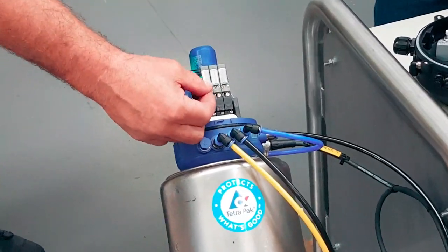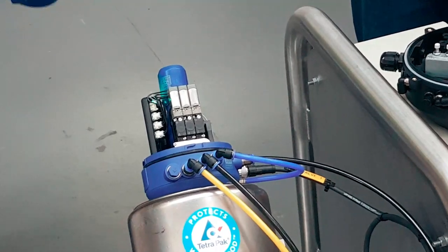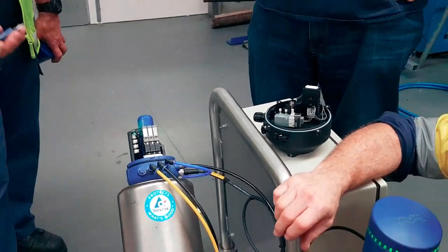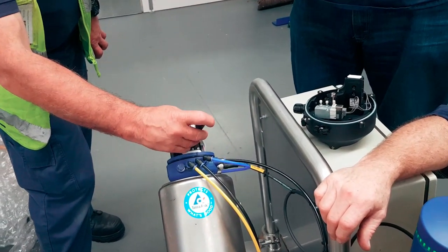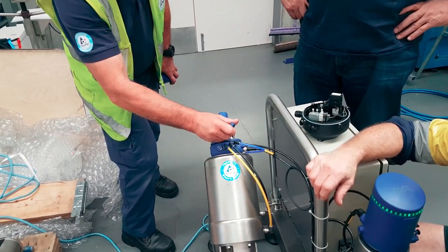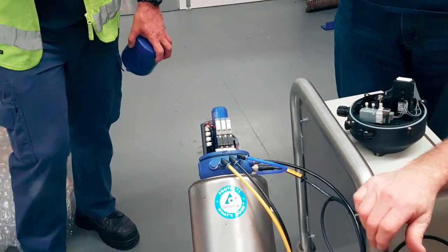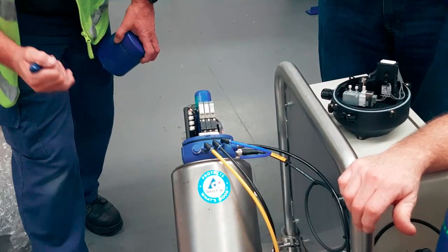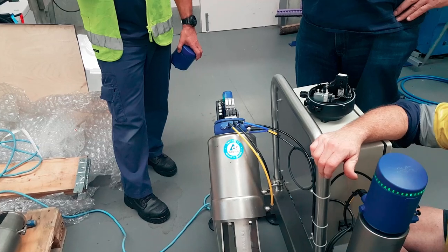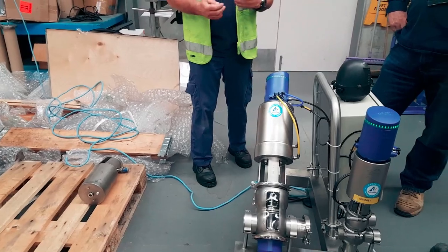I prefer a little toggle. Yeah, you physically put your finger on it and you move it. What happens is you can get it off quick, and in an emergency, you can. If you don't get the screwdriver in the slot, will you? Yes, and what happens is that, of course, everybody gets in and has a play with these, and in no time that slot becomes wrecked. Or, as happened in the root cause of this case, the guy had it on, a vibration came, he bumped the valve, or someone bumped the valve, and that unclipped. And he actually tore his finger off.